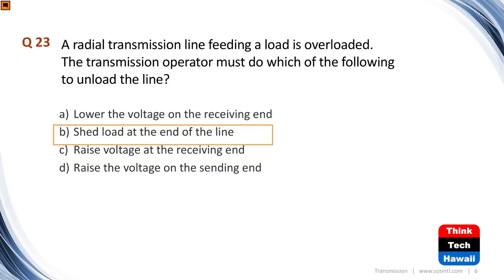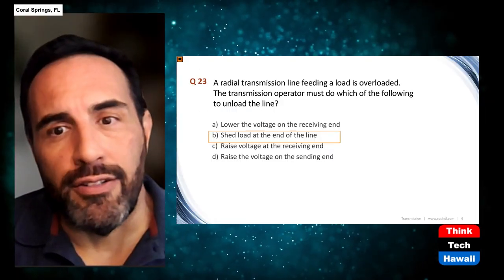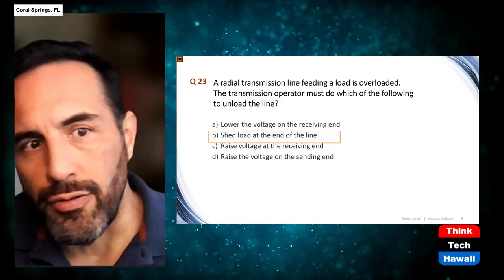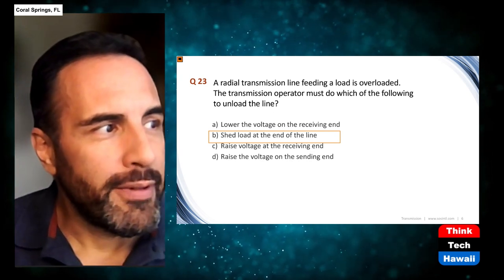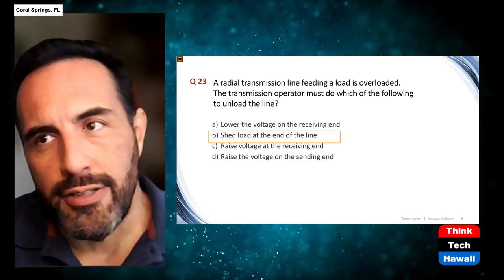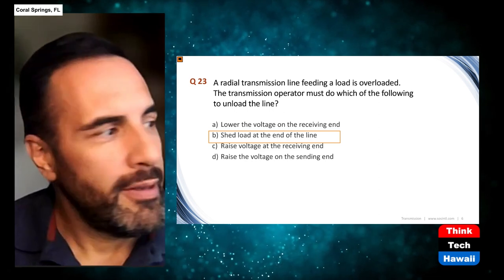Other than that, there's no other solution, right? Lower the voltage to the receiving end, that won't help you at all. In fact, that'll probably bring about a collapse, right? Raise voltage at the receiving end, that has very limited effect and really won't do much because the load is real and the load's still there. Raising voltage in the sending end is the same problem. You might actually aggravate such things because now you're going to send power over to the load. So again, shedding load at the end of the line is the only solution in this case.